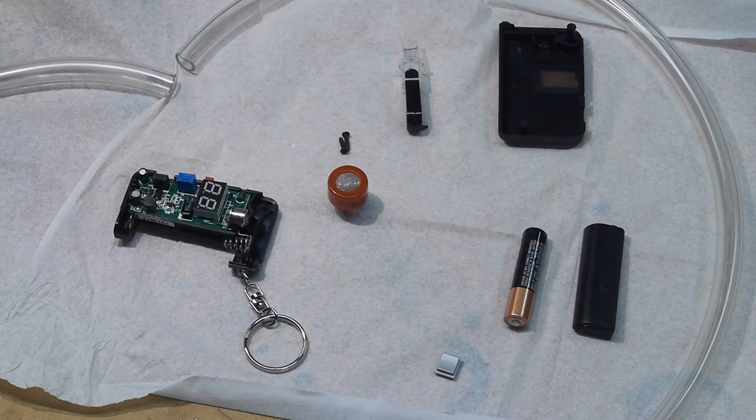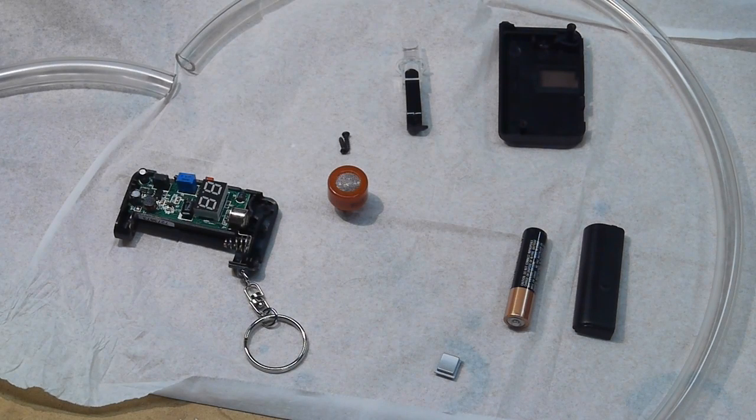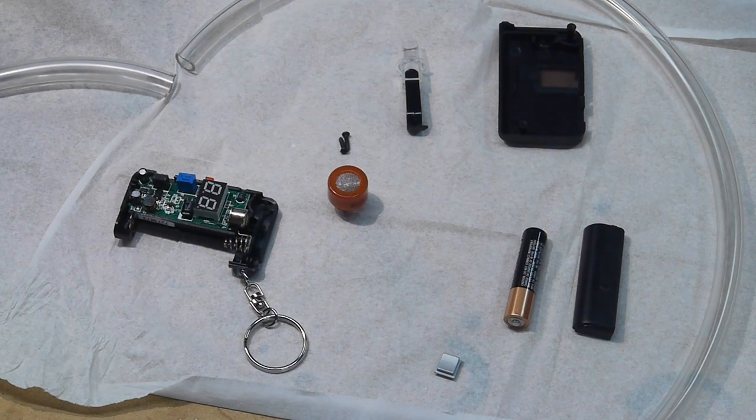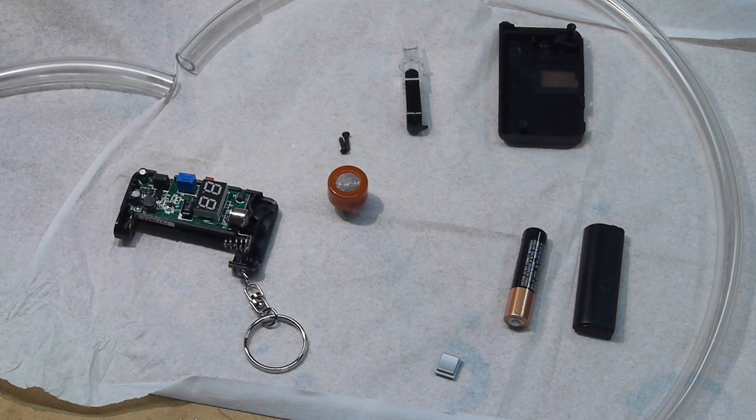So that may make you think that the oxygen concentration of the gas coming in is important, and it certainly is. The data sheet shows that the oxygen concentration is very critical to the performance of this thing, and they've been calibrated for atmospheric air, about 20 percent oxygen. If you blow higher concentrations of oxygen at it, it will not read correctly, in addition to lower concentrations. It's also temperature and humidity sensitive, and those variables have been calibrated for breath, so relatively high humidity and temperature of 20 something or 30°C.